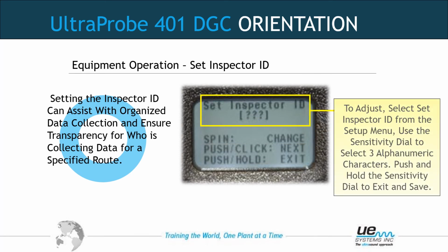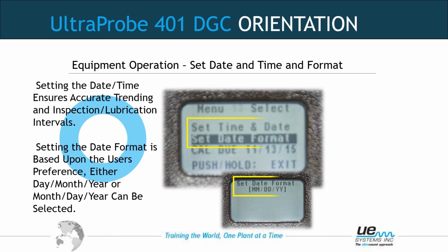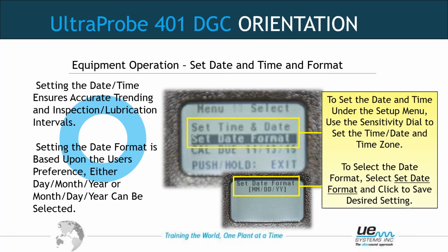Inspector ID. This could be important information. If we have multiple hands on this unit, who took these readings? You set it once and then take your readings and download. That will go in the software with 3 alphanumeric characters. Maybe it's initials, but you can change what those are here. Next item down would be set date format, and that is month, day, year, or day, month, year. How do you want the date to appear? It should match whatever your computer is.